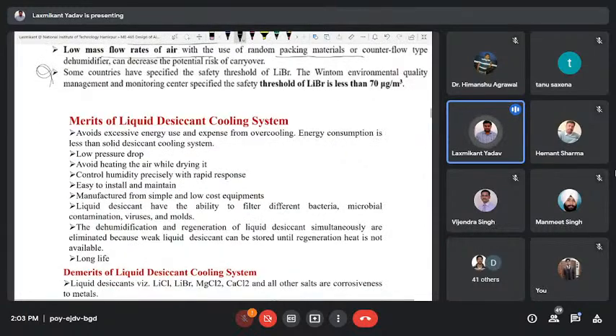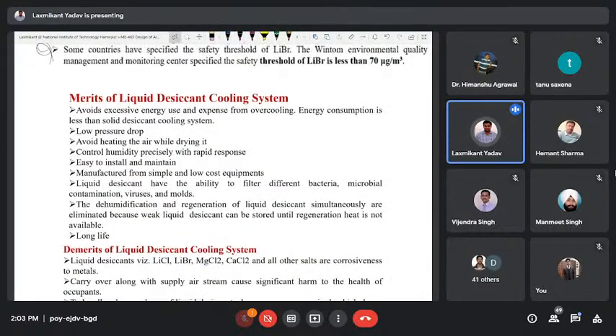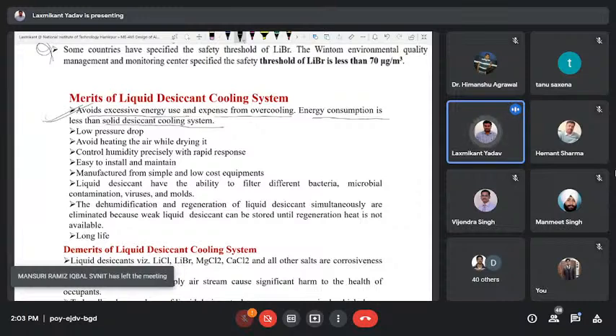so what are the merits of liquid desiccant cooling system? Avoid excessive energy use and expense from overcooling. Energy consumption is less than solid desiccant cooling system. So this is the outcome of different research that is carried out in the field of liquid desiccant. Low pressure drop as compared to solid. Avoid heating in the air while drying it. Okay, so heat of adsorption is less as compared to solid desiccant.